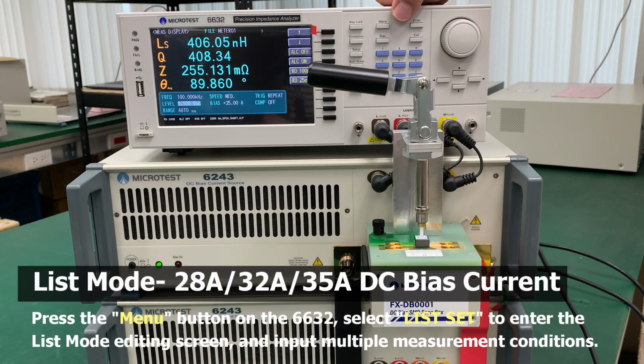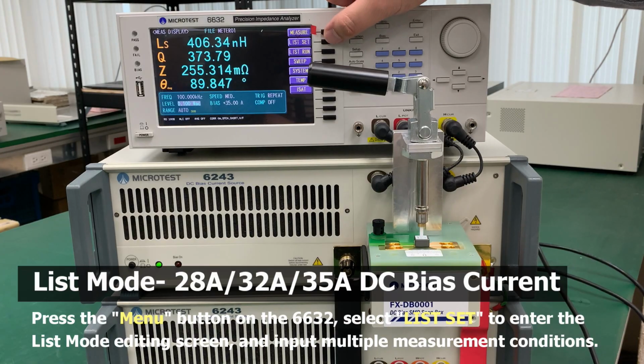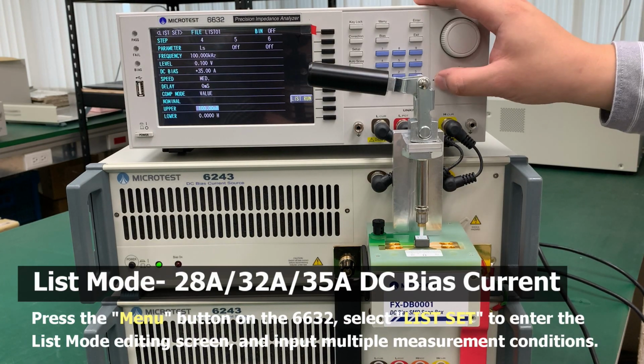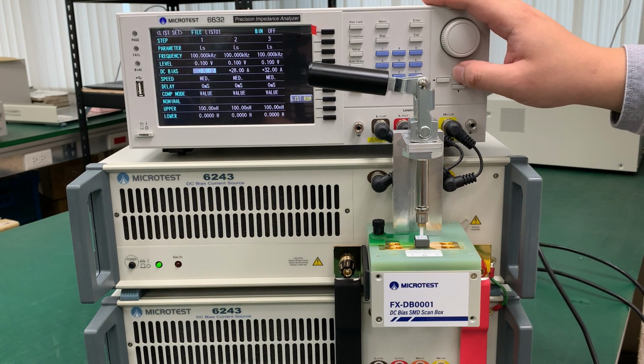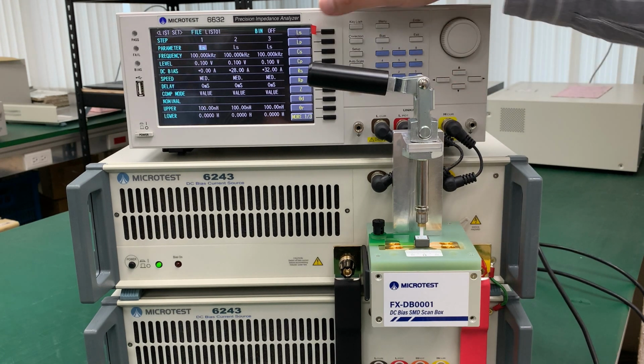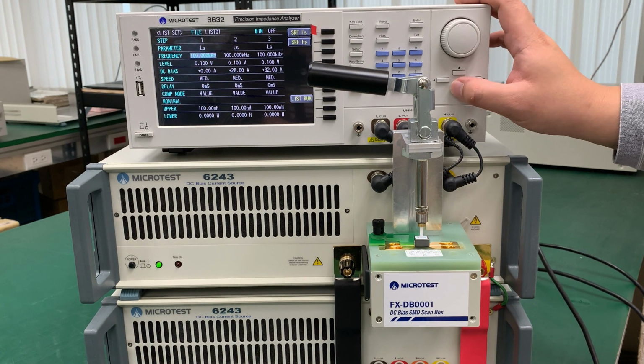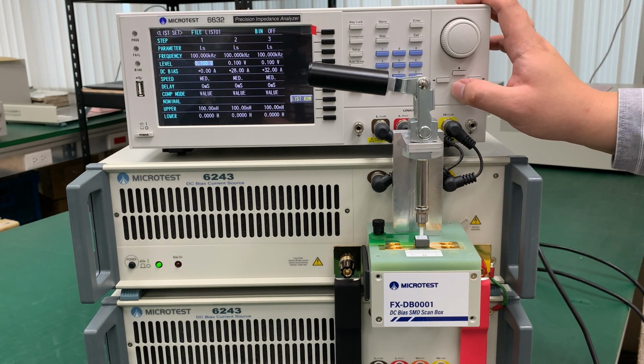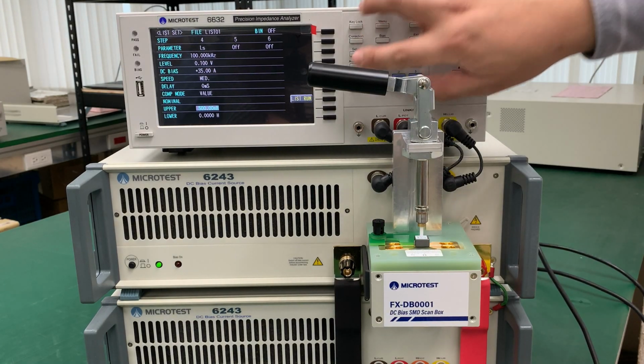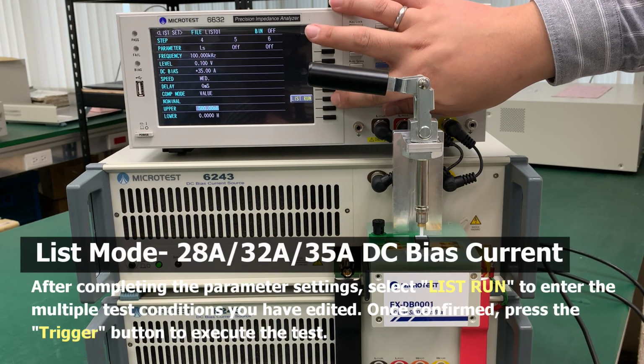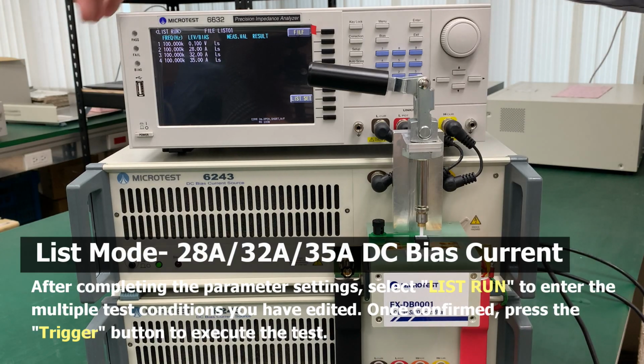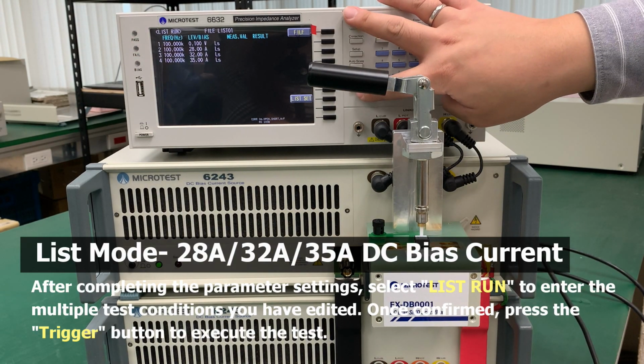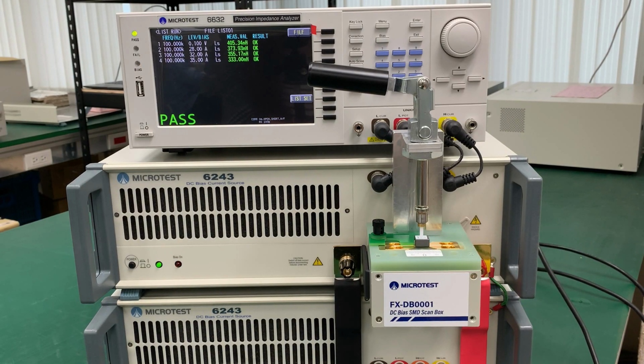Press the menu button on the 6632. Select List Set to enter the list mode editing screen, and input multiple measurement conditions. After completing the parameter settings, select List Run to enter the multiple test conditions you have edited. Once confirmed, press the trigger button to execute the test.